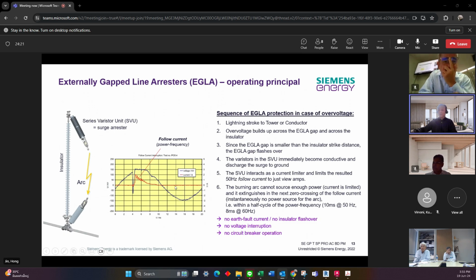So from this curve, you can see the working curve exactly. After that, we have a follow current, because the arcing current should be extinguished. And this extinguishing will be tested by the follow current interruption test. It belongs to the type test.